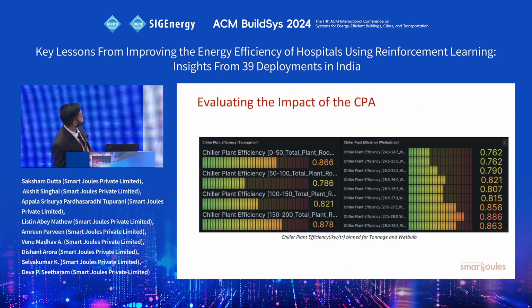So as you can see, this is one of the visualizations from a site where we have binned the data for chiller plant efficiency. This is binned for tonnage and wet bulb. You can see this is for 0 to 50, 50 to 100, 100 to 150, and 150 to 200. And on the right, you can see the wet bulb bins in 0.5 degree steps. This way, once we have this binned data, we could compare T1 and T2 and compare different parameters such as the chiller efficiency or the equipment efficiency directly one-to-one. This normalization helps us evaluate.